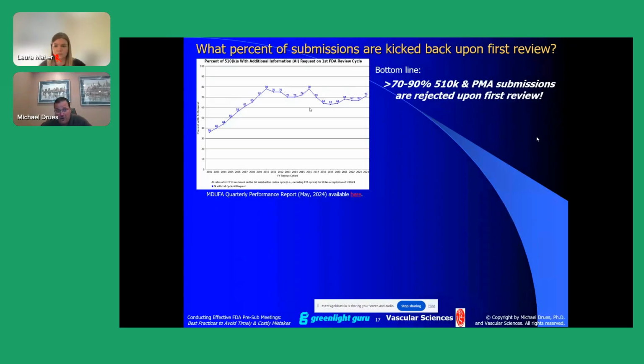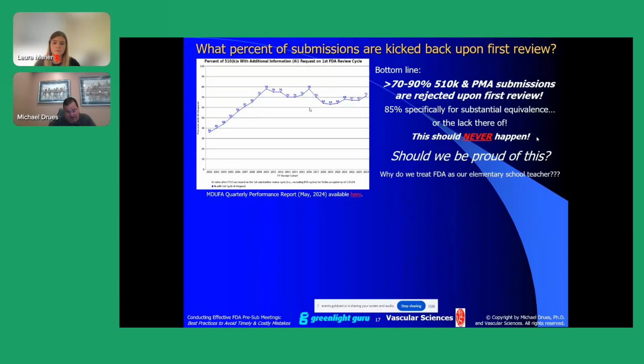But back to the question of why is this so important? Well, what percent of submissions are kicked back after their first review? For those of you that work in the 510K world, this is the most current data on that. You see that a little more than 70% of 510Ks that are submitted to the FDA today are rejected first time out of the box. 70%, and this number has fluctuated plus or minus about 10% for the last 20 years or so. So the question is, is this progress? And in the 510K world, when you look at those 70-odd% that are rejected, about 85% of them are rejected specifically because of substantial equivalence or the lack thereof.